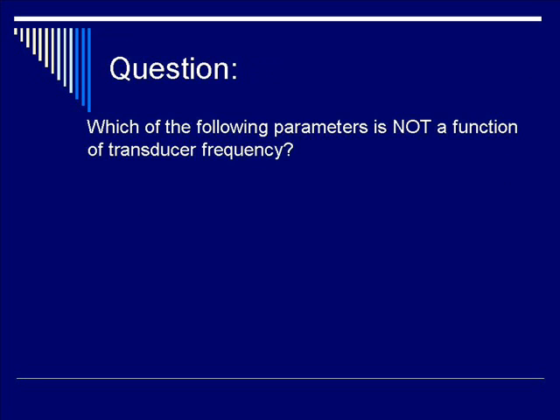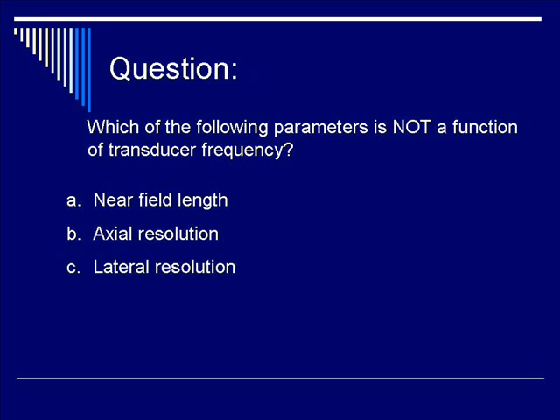Let's do a question. Which of the following parameters is not a function of transducer frequency? Is it A, near-field length? Is it B, axial resolution? Is it C, lateral resolution? Or is it D, slice-thickness resolution? Think back on all the different components that we discussed so far in this lecture, and ask yourself which one is not a function of frequency. The correct response is D, slice-thickness resolution.